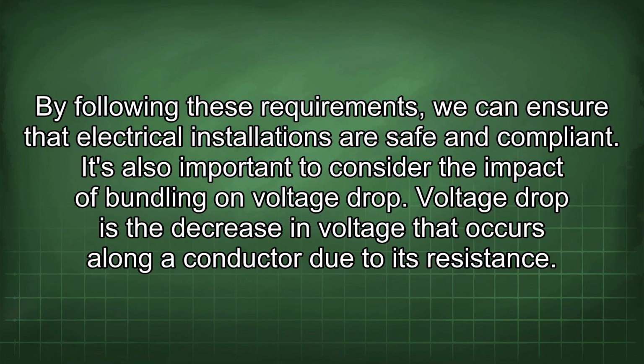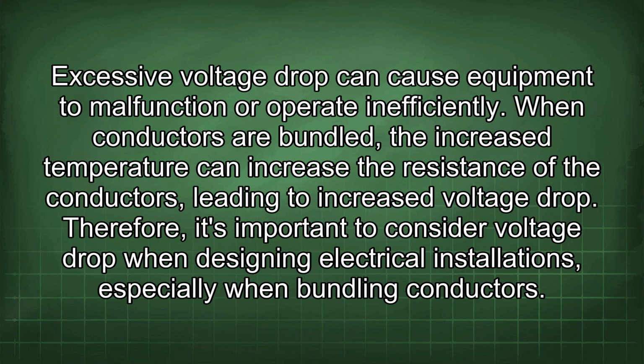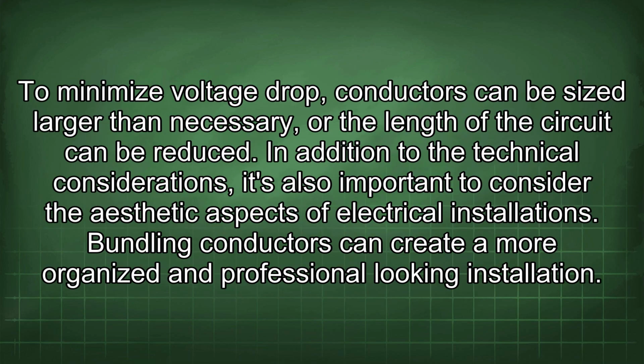It's also important to consider the impact of bundling on voltage drop. Voltage drop is the decrease in voltage that occurs along a conductor due to its resistance. Excessive voltage drop can cause equipment to malfunction or operate inefficiently. When conductors are bundled, the increased temperature can increase the resistance of the conductors, leading to increased voltage drop. Therefore, it's important to consider voltage drop when designing electrical installations, especially when bundling conductors. To minimize voltage drop, conductors can be sized larger than necessary, or the length of the circuit can be reduced.